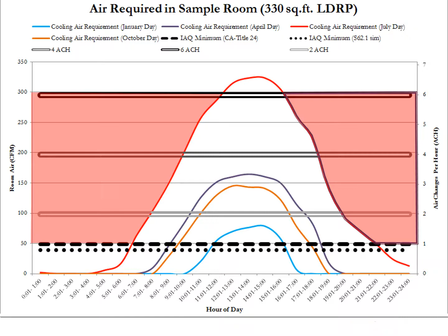But what's more interesting still is to take a look around the world at labor and delivery spaces—what are all the different requirements you could find? The French are the strictest; they call it a risk category 3, so they're actually validating particle counts and microbial counts when they get into labor and delivery spaces. I think that's excessive. The UK, for whatever reason, wants 15 air changes per hour. I think that's a carryover from when they were doing surgeries in the LDR rooms.